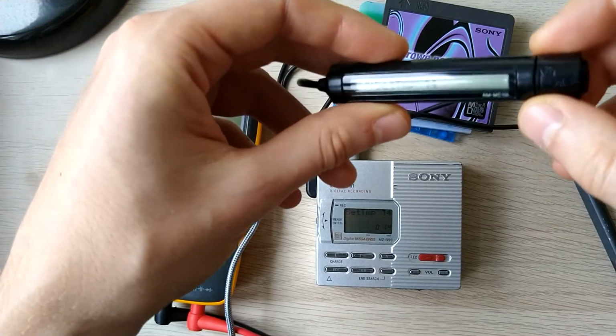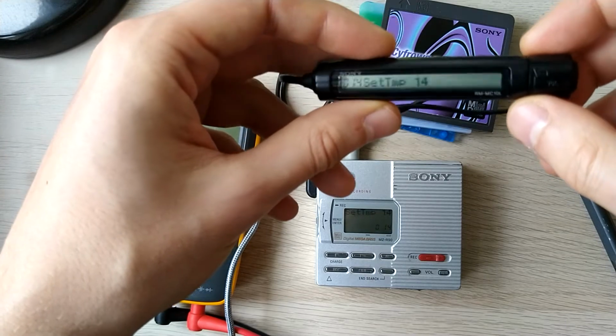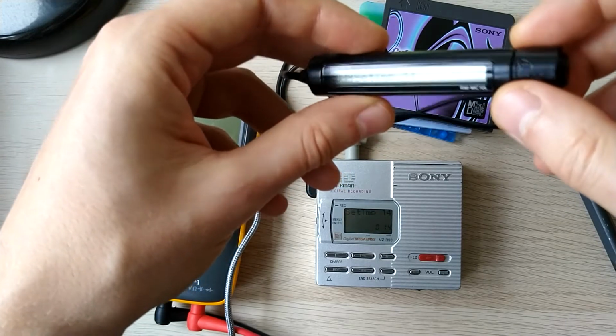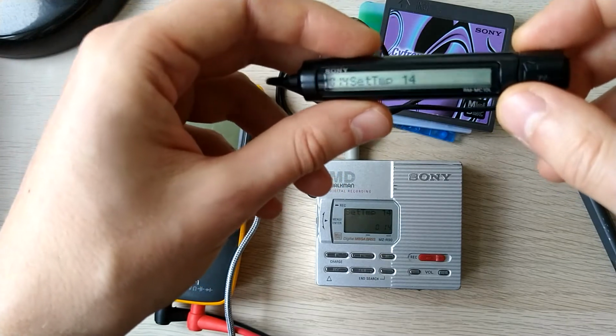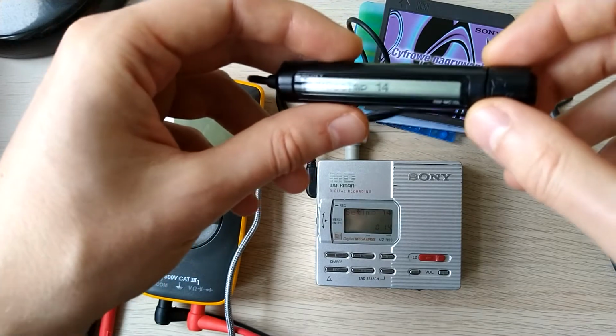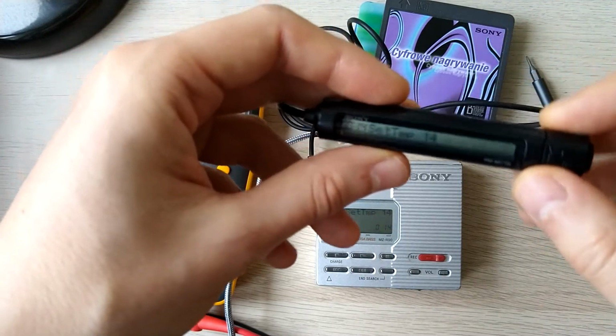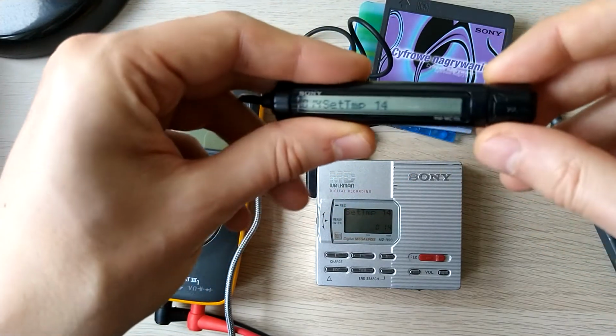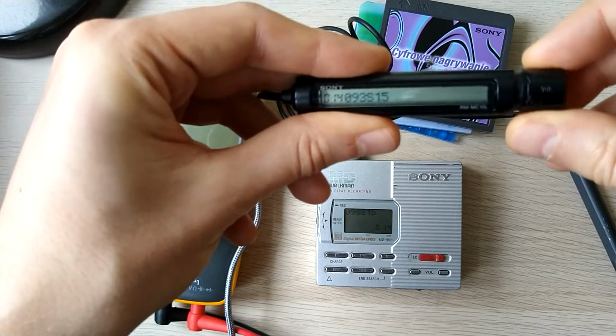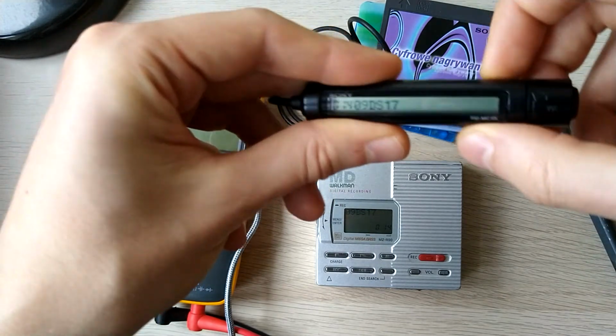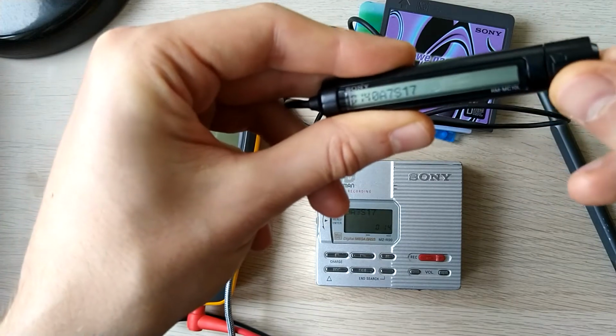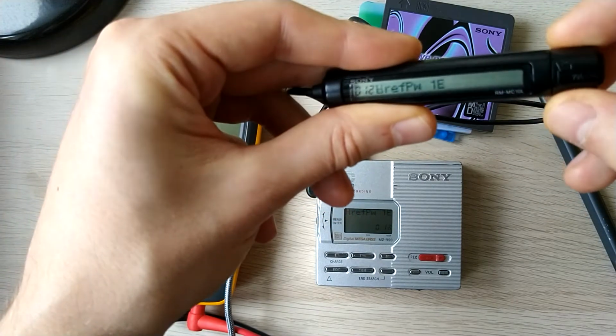014, which is set temp, and it currently shows 14. The value is expressed as a hexadecimal, so this is in fact 20 degrees Celsius. In my room currently it's 23 degrees, so I'm going to move this value up by 3 and confirm by pressing pause. And that's the temperature calibration done.